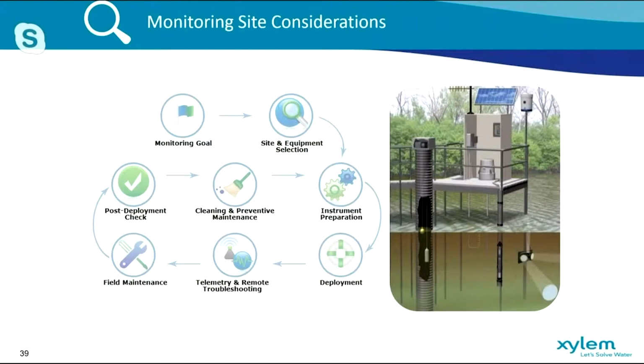At the sensor level, for in situ monitoring equipment, we need to look at what happens to it after we bring the sensors back - how often do we need to calibrate them, how often do we need to perform maintenance. This can be figured out after the first deployment and then fine-tuned.